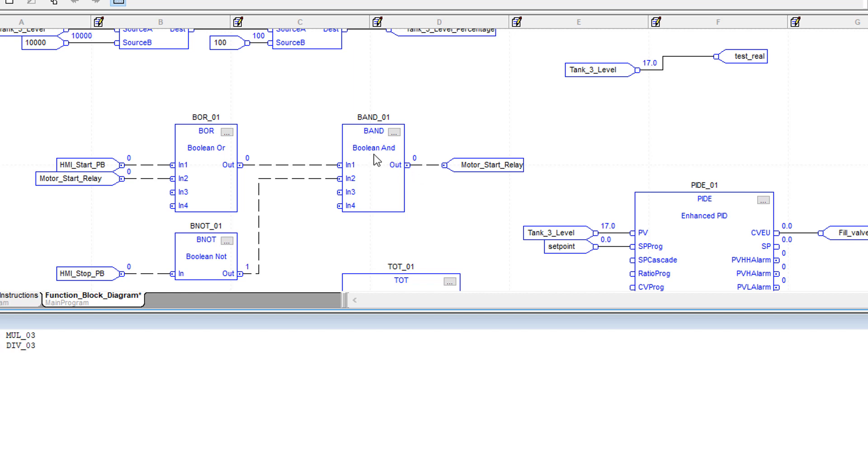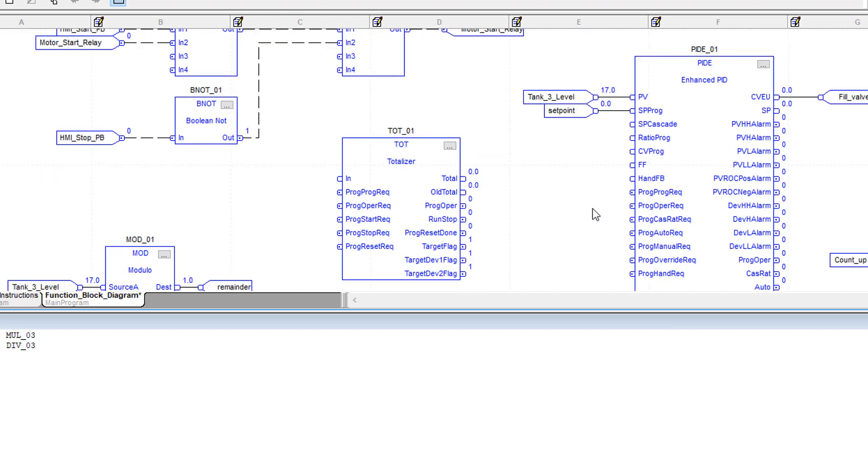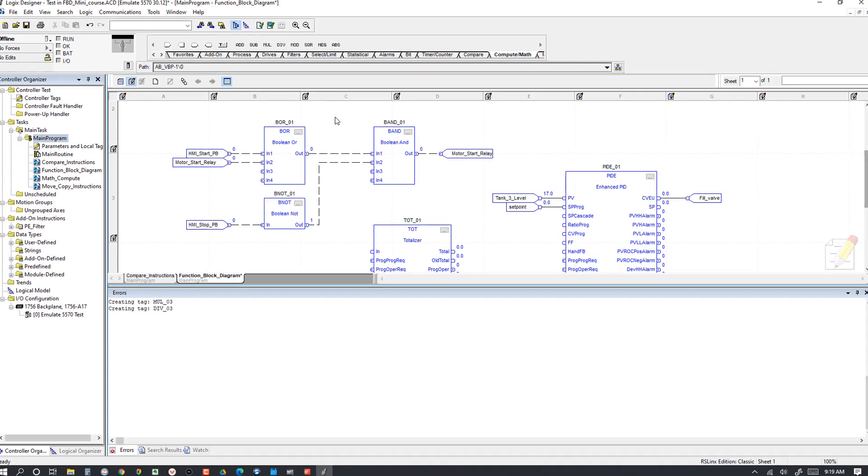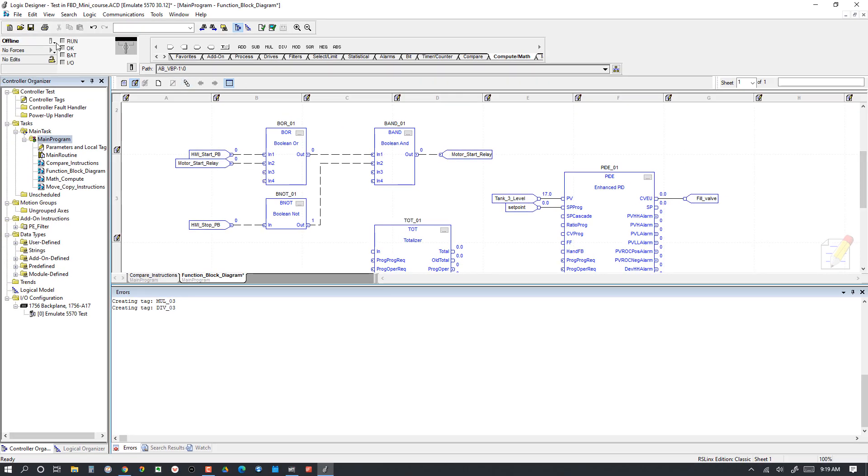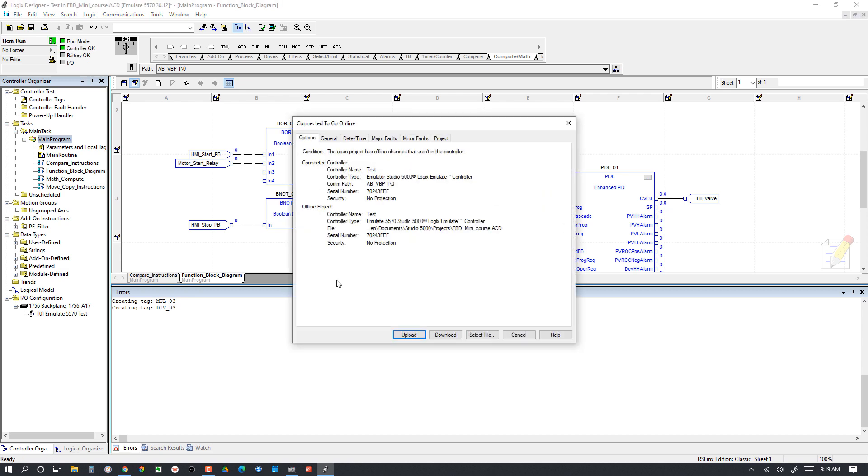With our Boolean NOT, that's pretty simple. You just have one input and it's going to flip it from a zero to a one or a one to a zero. Then the output of the Boolean NOT and the Boolean OR go to a Boolean AND. From there you AND them together, which means they both must be true for the output of the Boolean AND to be true, or else it's going to be false. This is mimicking a basic motor start latch in circuit or a make seal break circuit. It's just a seal in logic. Let's run it and show you how it works here.